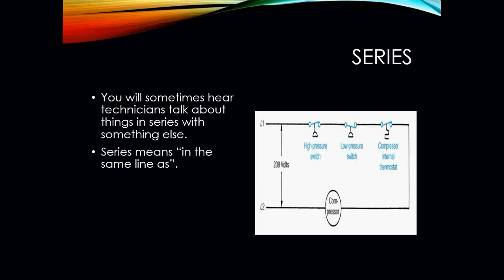The first topic that we need to understand is a series circuit. Sometimes you will hear a technician talk about things being in series with something. When we hear that word series, it means that they are in the same line next to each other, one right after another. As you can see in the picture here, we have a high pressure switch, a low pressure switch, and an internal compressor thermostat. Those are all wired in series with each other. So in order for the compressor in this diagram to come on, that high pressure switch, that low pressure switch, and that internal thermostat all have to be in the closed position in order for voltage to even make it to the compressor.